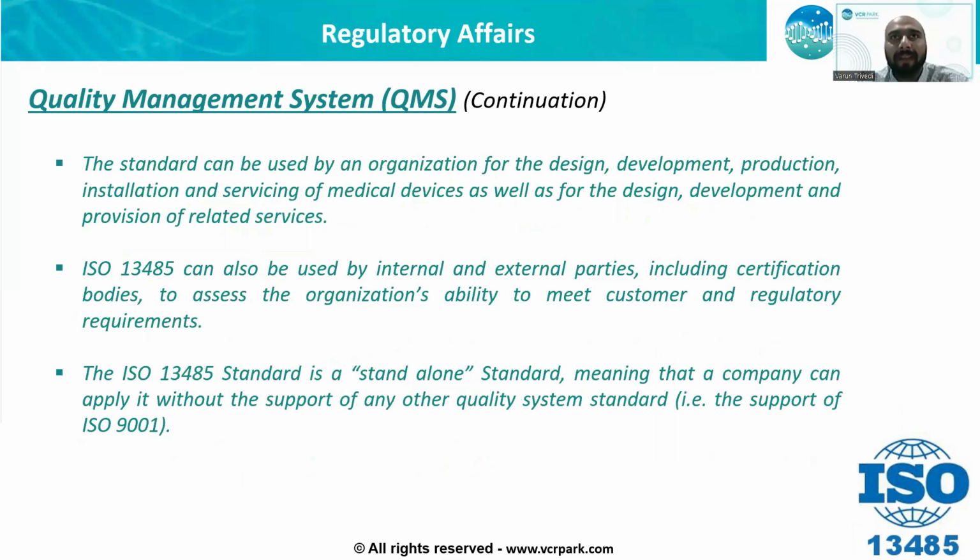There might be a case where there is no installation and servicing needed. In such a scenario, those requirements from ISO 13485 are not applicable. The organization needs to say that and also give a justification as to why it is not applicable. The standard can be used by internal and external parties, including certification and regulatory bodies, to ensure that the required expectations are met from a regulatory requirement perspective and also from a certification perspective. It's a standalone standard. What it means is that it is a standard against which an organization can claim their certification and show the compliance against 13485.